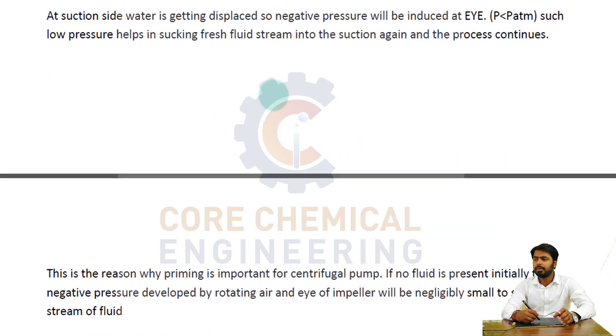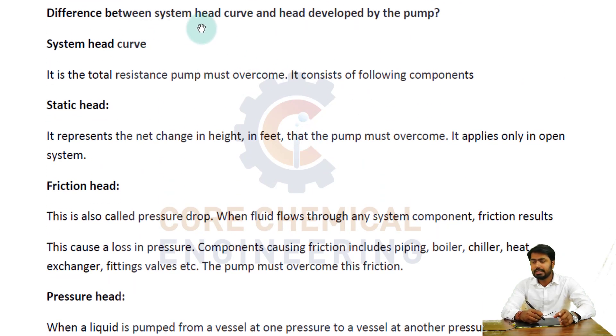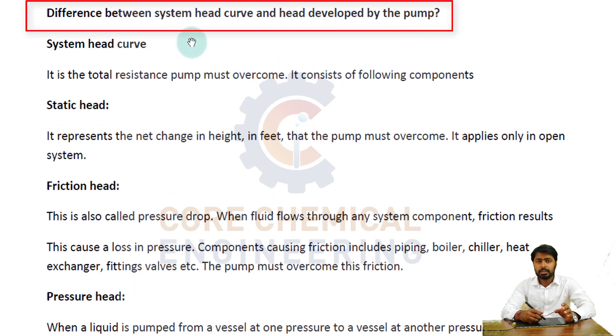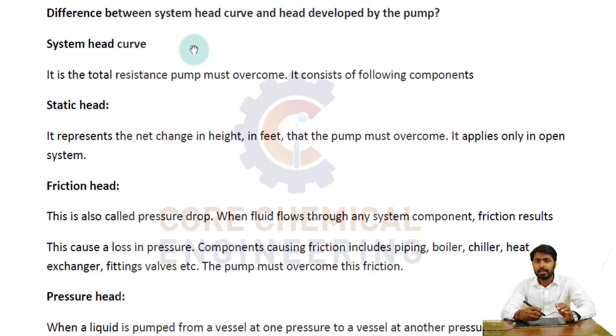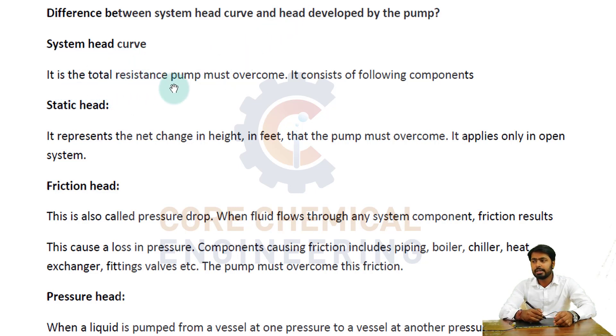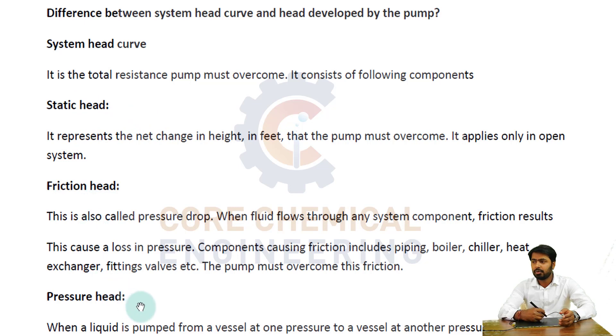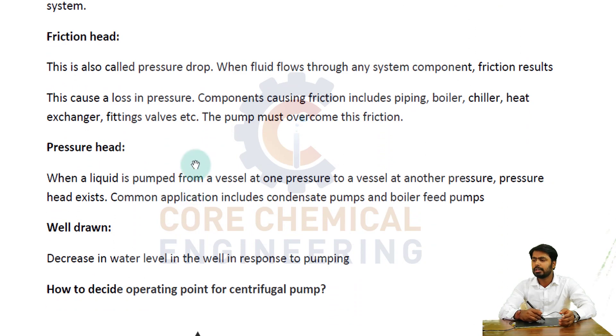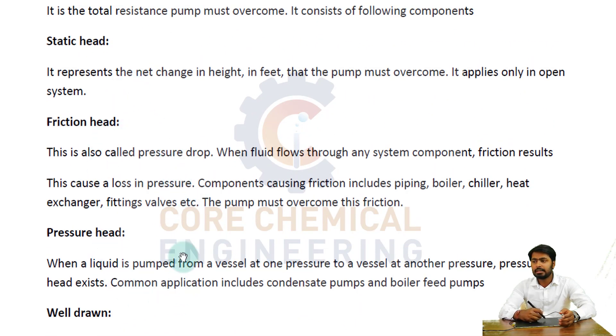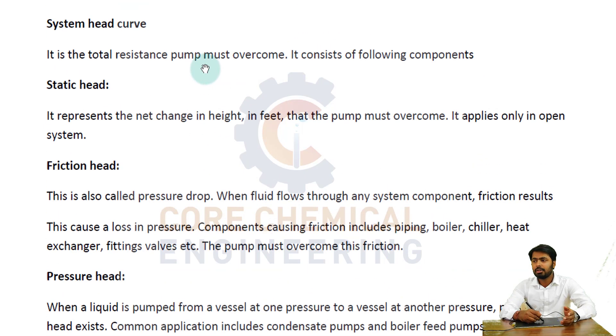Now we will discuss the difference between the system head curve and the head developed by the pump — these two are very important. The system head curve is the total resistance the pump must overcome. It consists of the following components: static head, friction head, pressure head, and well drawdown. These resistances are represented in terms of feet of head, and that is called the system head curve.